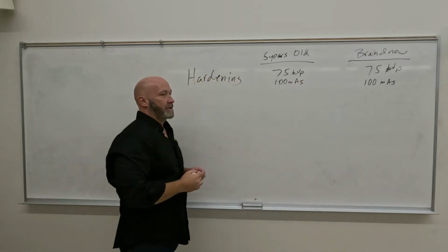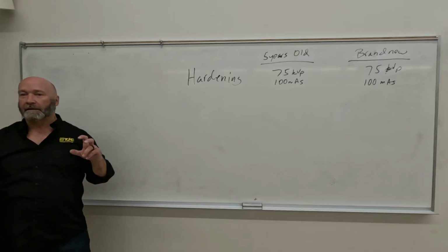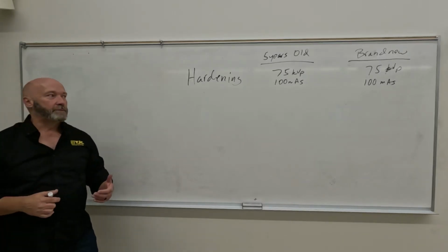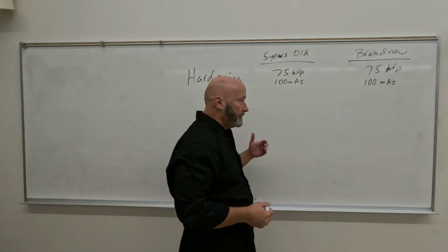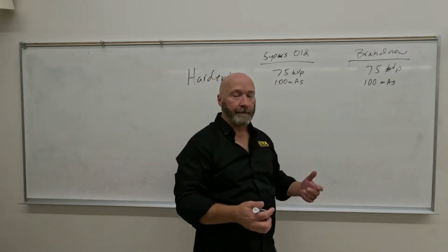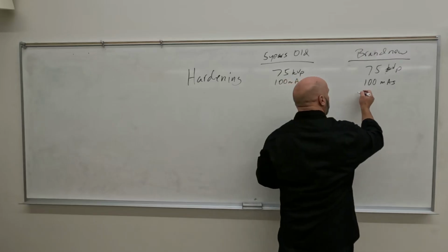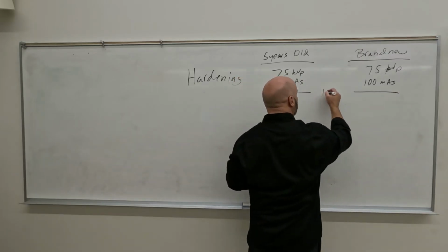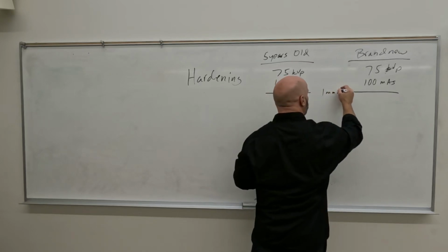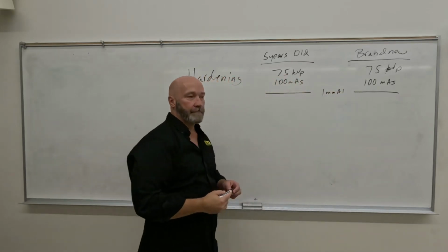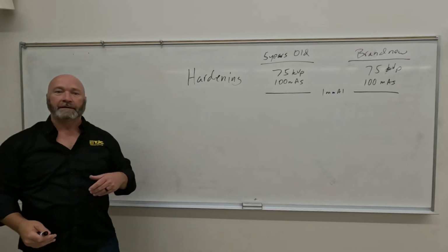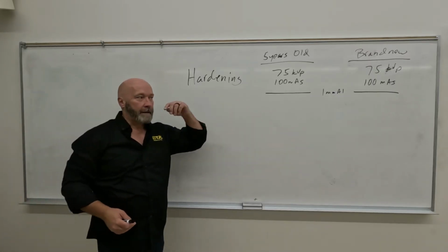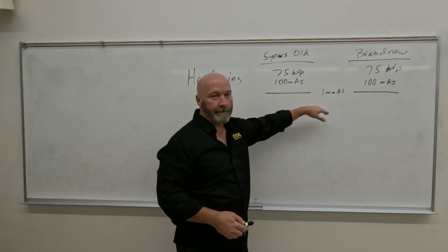Now we want to measure the quality of the x-ray beam. So we're going to take layers of aluminum, put one here and one here, exactly the same, and let's say they're 1 millimeter of aluminum, or some material that would absorb x-rays equivalent to aluminum.